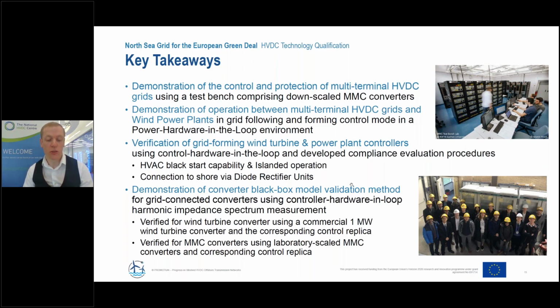The demonstration of a converter black box model validation method for grid connected converters used controller hardware in the loop harmonic impedance spectrum measurement. They verified the wind turbine converter using a commercial 1 megawatt wind turbine converter and the corresponding control replica, and verified the MMC converters using the lab scaled MMC and corresponding control. Overall the method worked well, but it highlighted that models aren't always sufficient and you're better with measurements from a real controller.